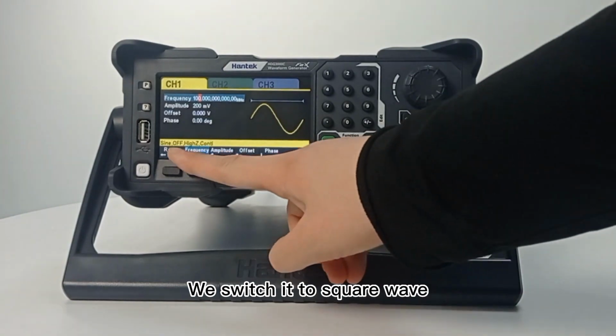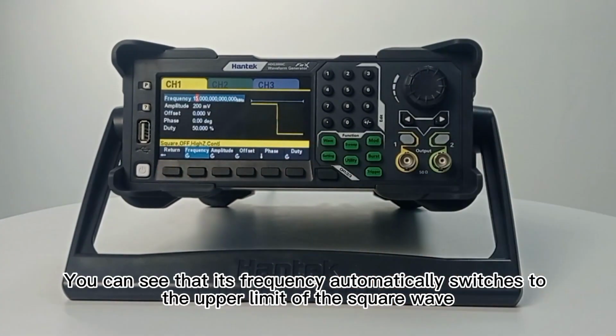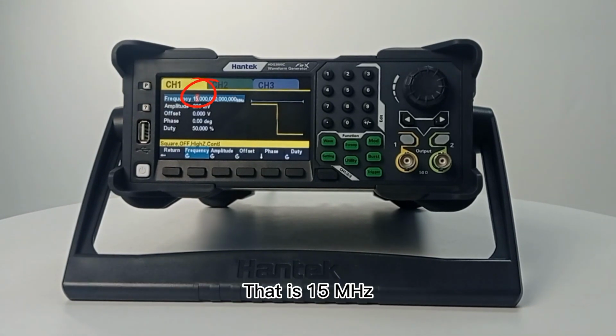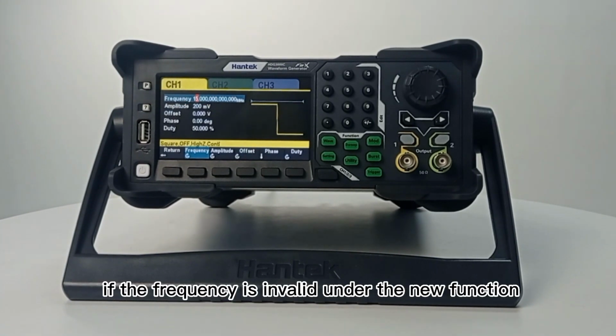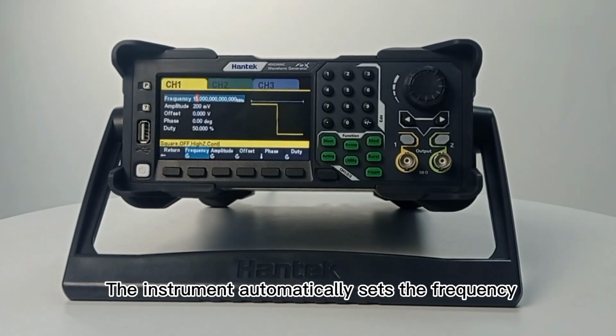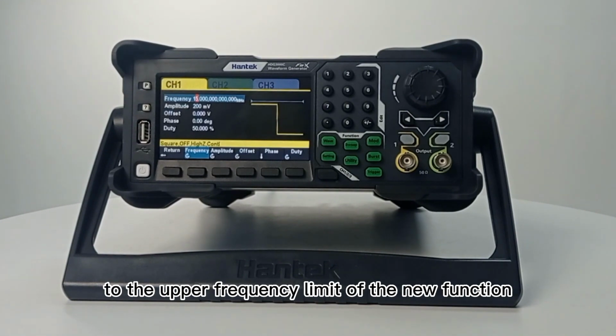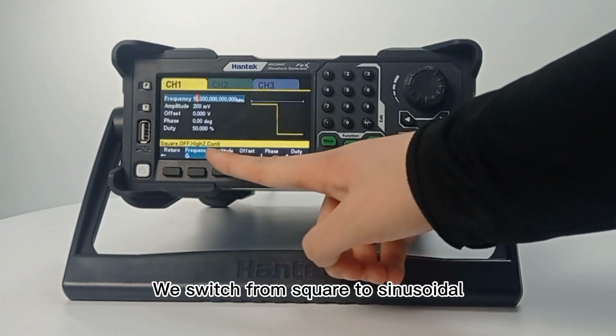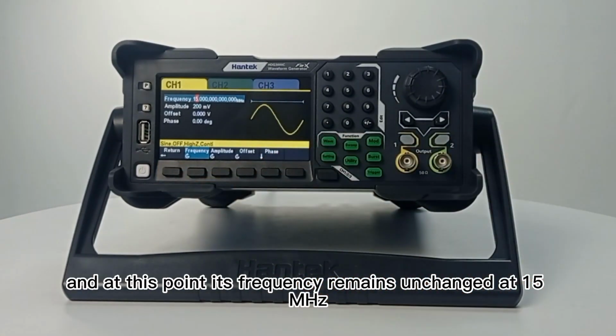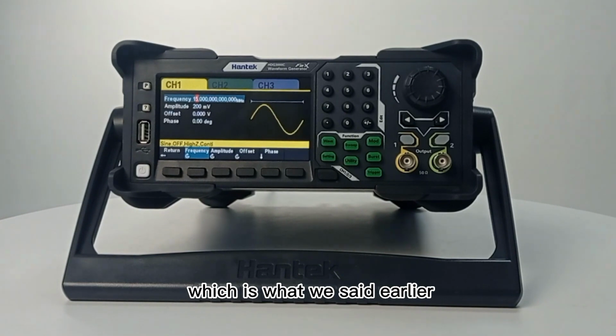We switch it to square wave. You can see that its frequency automatically switches to the upper limit of the square wave, that is 15 MHz. This is what we said earlier. If the frequency is invalid under the new function, the instrument automatically sets the frequency to the upper frequency limit of the new function. We switch from square to sinusoidal, and at this point its frequency remains unchanged at 15 MHz, which is what we said earlier.